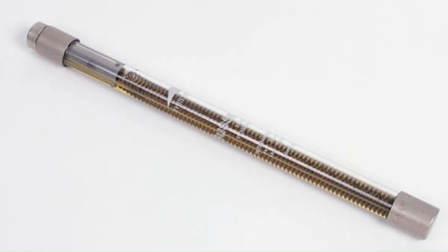Liquid type high voltage HRC fuse is filled with carbon tetrachloride and sealed at both ends with caps. When the fault occurs, the current exceeds the permissible limit and the fuse element is blown out. The liquid of the fuse acts as an arc extinguishing medium for the HRC fuse. They may be employed for transformer protection and the backup protection of the circuit breaker.